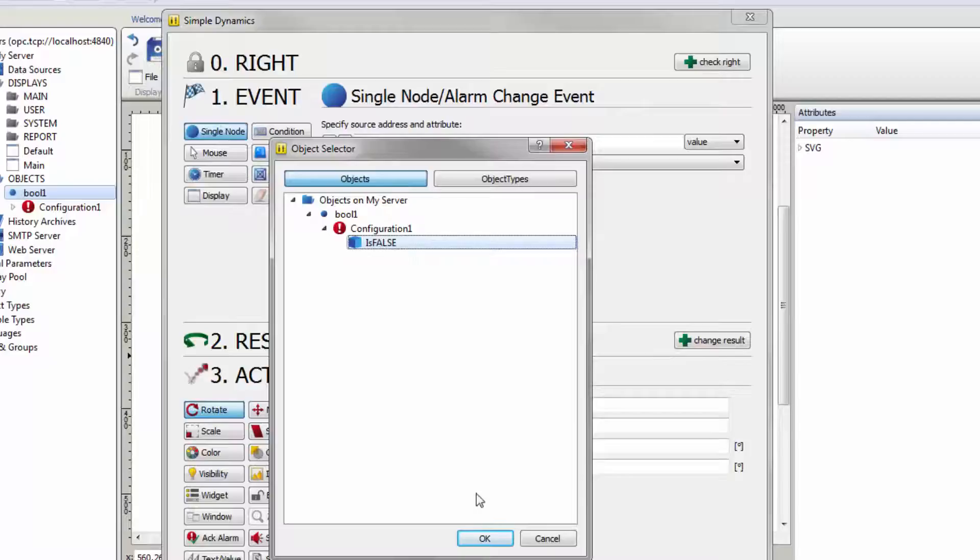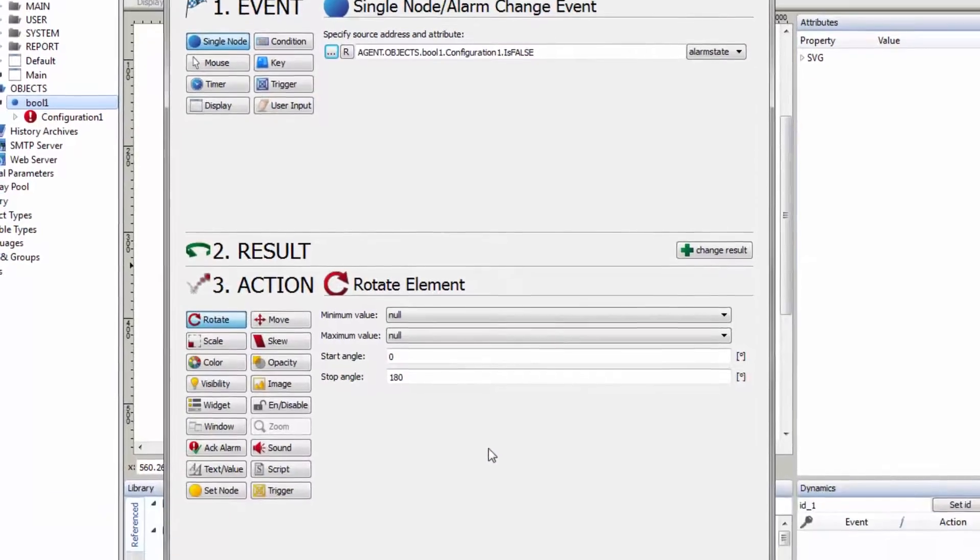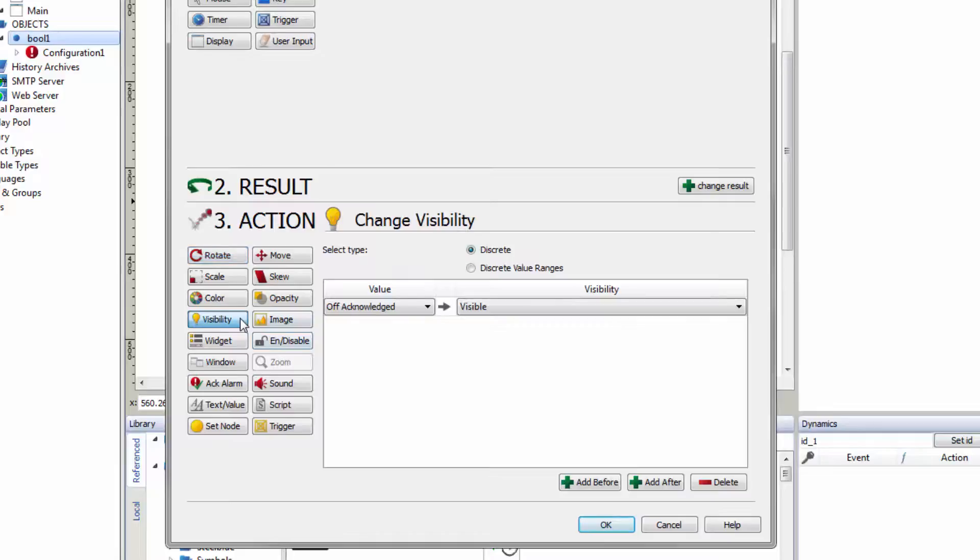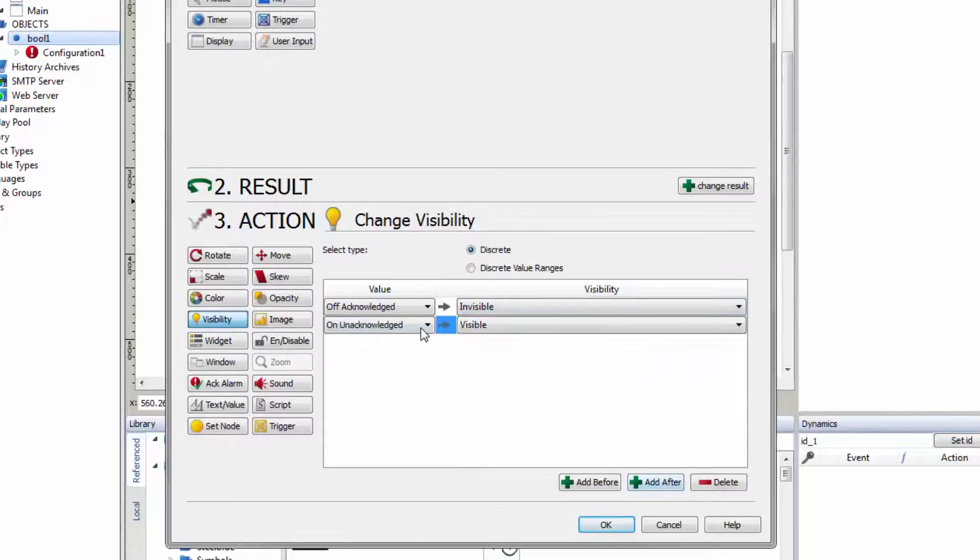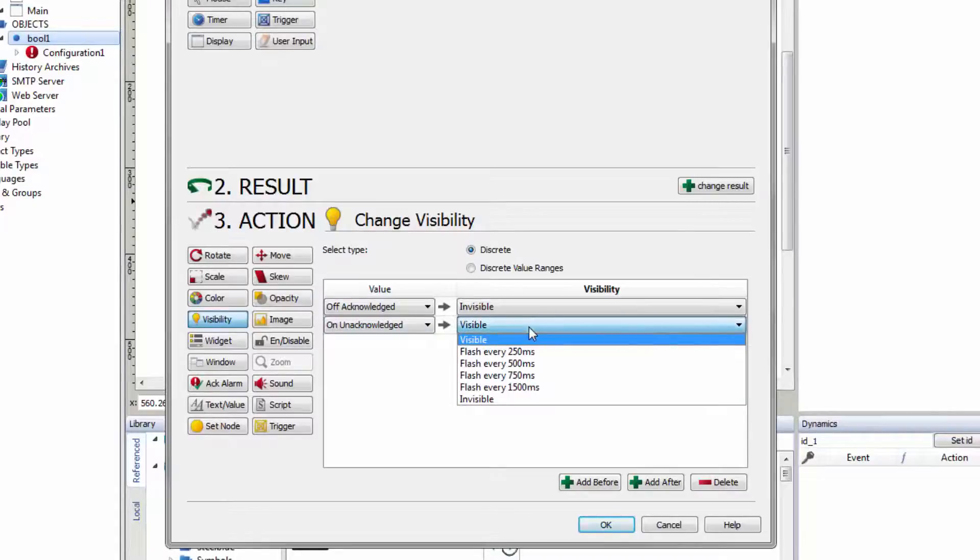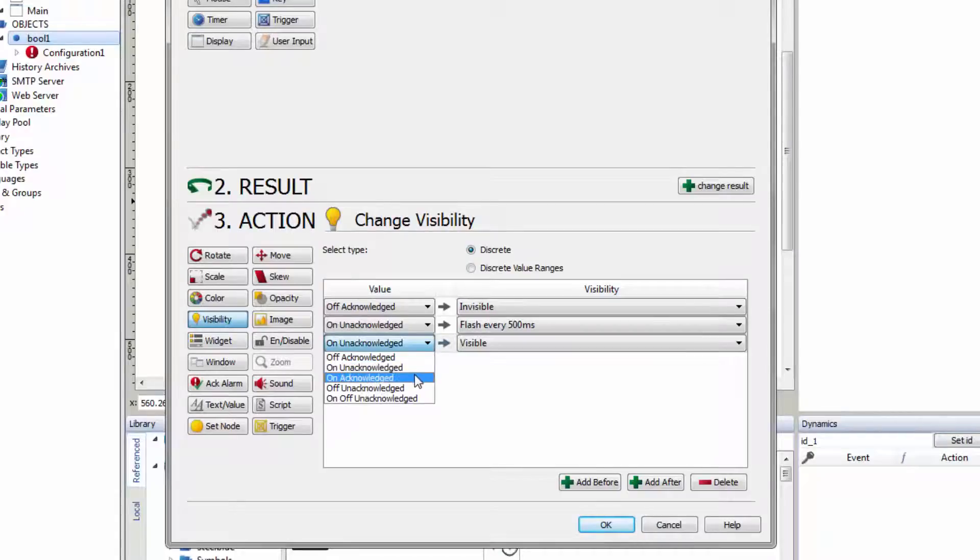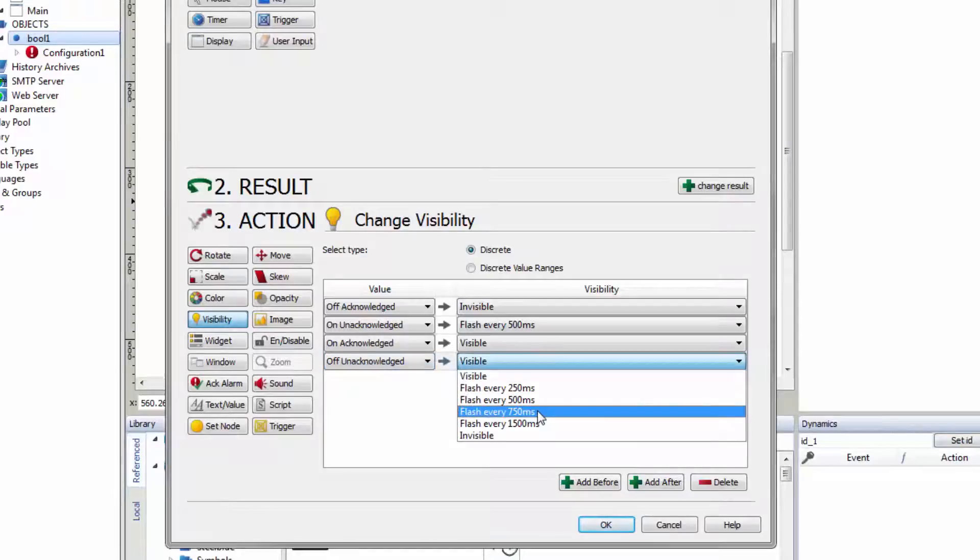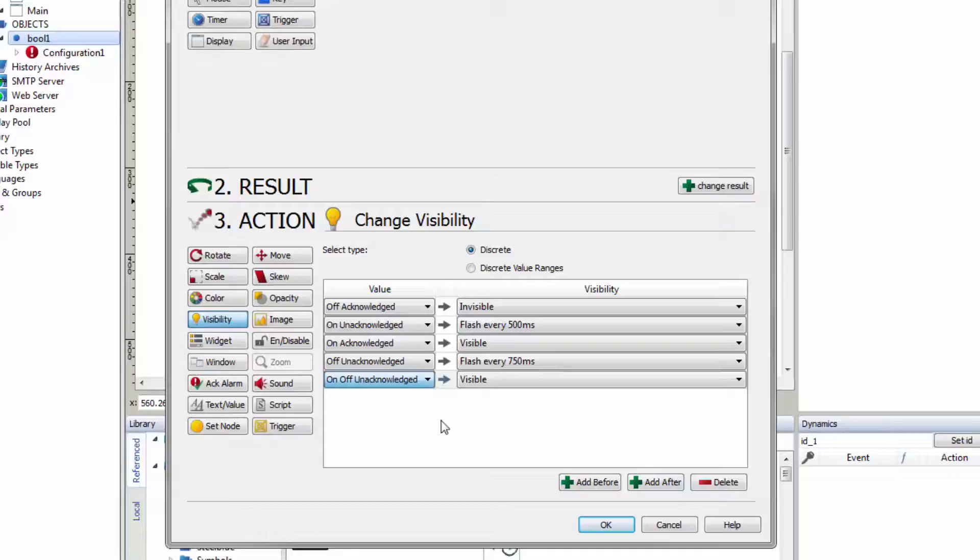Confirm your selection with OK. At the step Action, choose the type Visibility and set the following values. For Off Acknowledged, set the Visibility to Invisible. For On Unacknowledged, select Flash every 500 milliseconds. On Acknowledged, Visible. Off Unacknowledged, Flash every 750 milliseconds. On, Off Unacknowledged, Flash every 250 milliseconds.